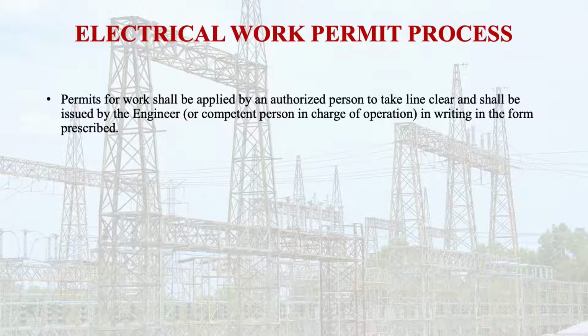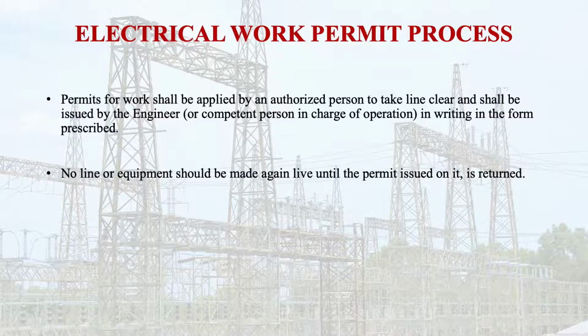Permits for work shall be applied for by an authorized person to take line clear and shall be issued by an engineer or competent person in charge of operation, in writing, in the form prescribed. No line or equipment should be made live again until the permit issued on it is returned. That means one has to return the permit also.